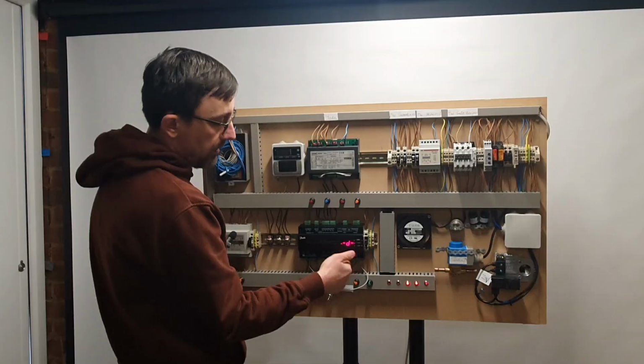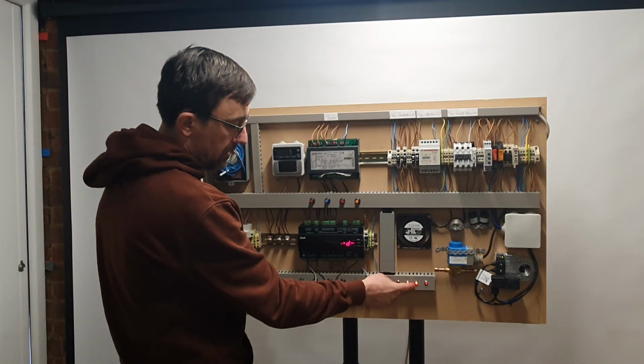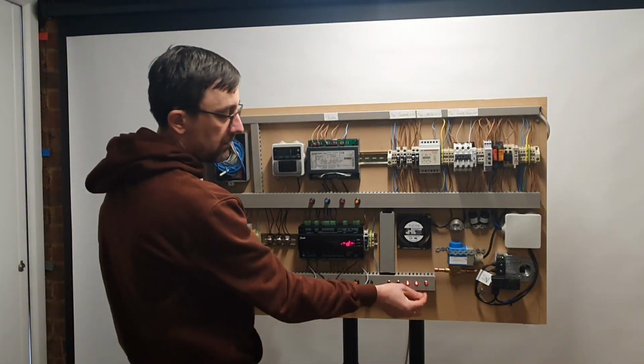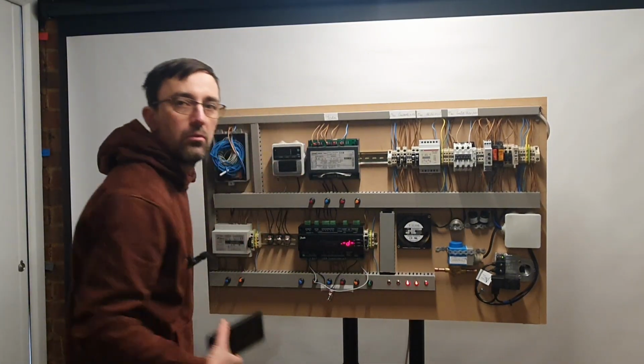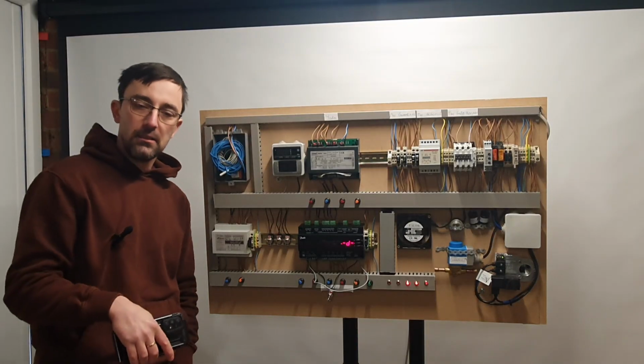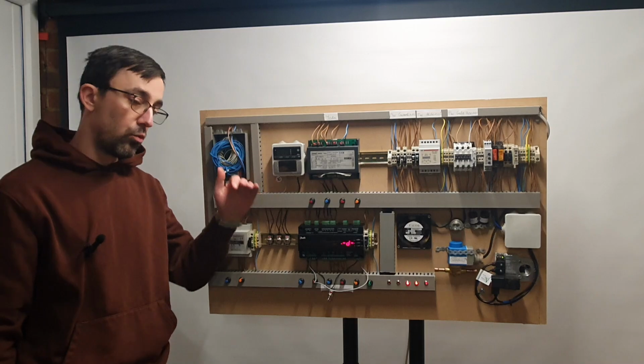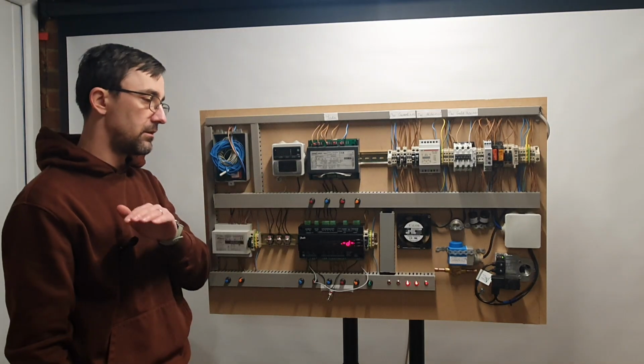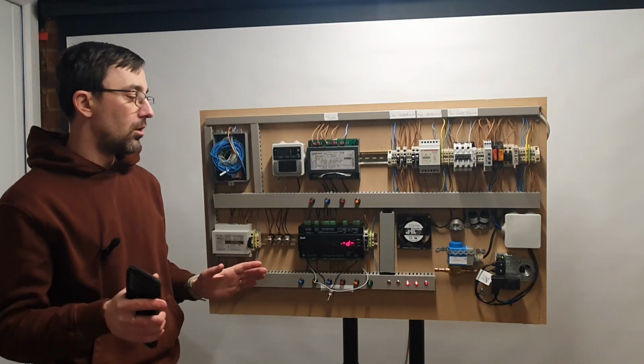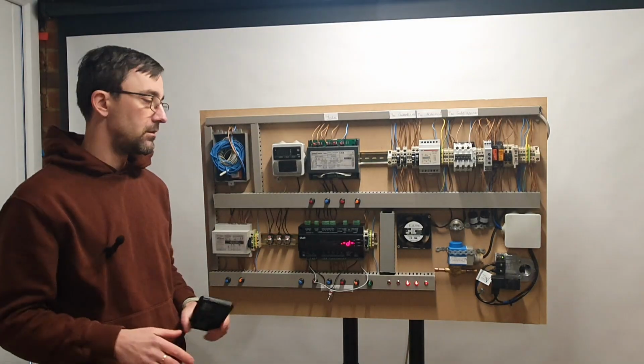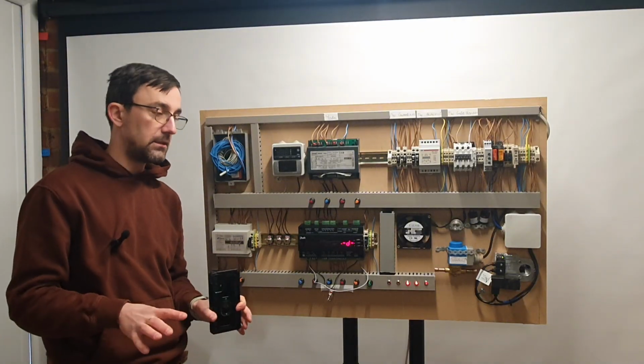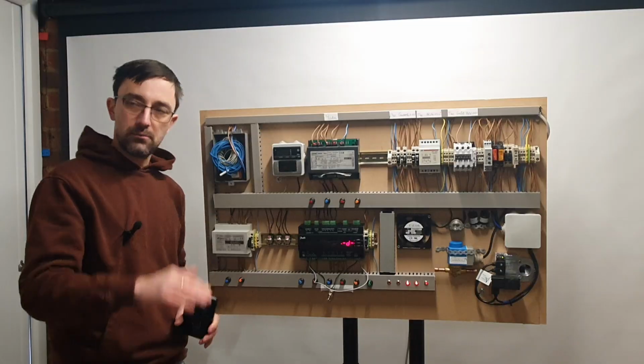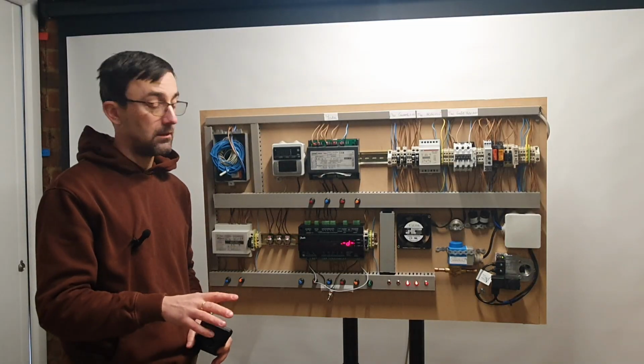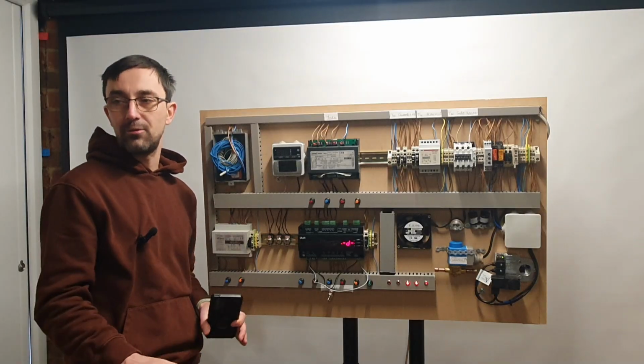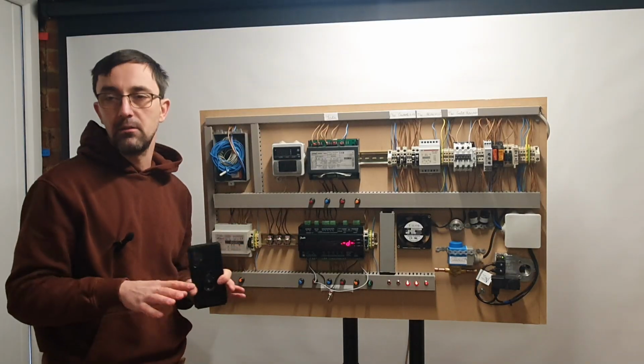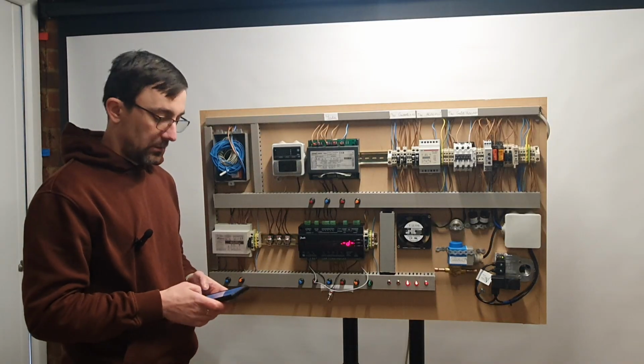So it's got a time delay after you force it on defrost. It brings the electric heaters on, if it's got some, but that's what this light is there for. So the defrost will terminate, it will stop, when the defrost temperature probe reaches its cutout set point. What you tend to find on some controllers is you give it a minimum defrost of 20 minutes. And then if the defrost termination probe reaches cutout, it will stop the defrost heaters from working, but the system will just sit there on defrost. So let's see if this is the case.